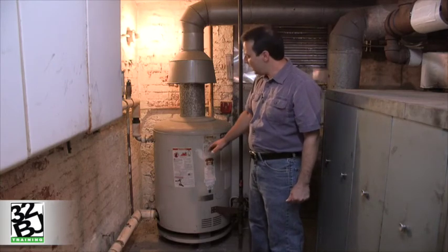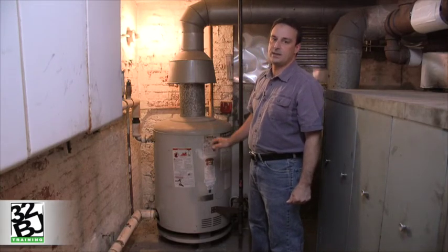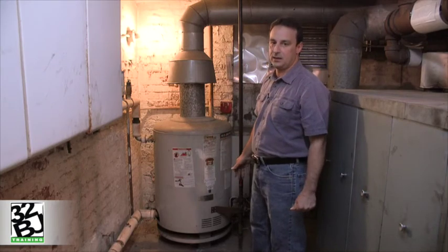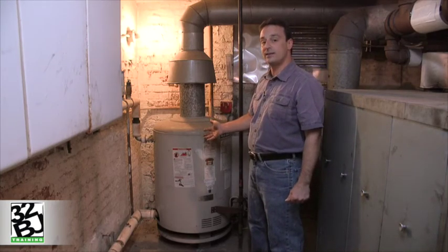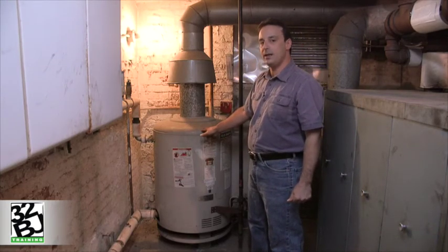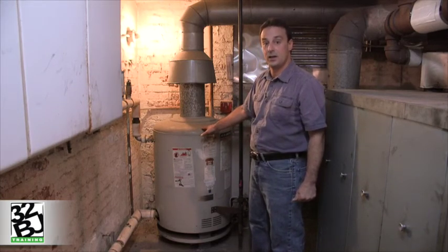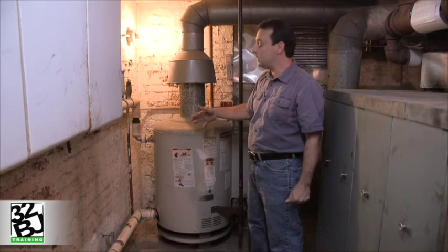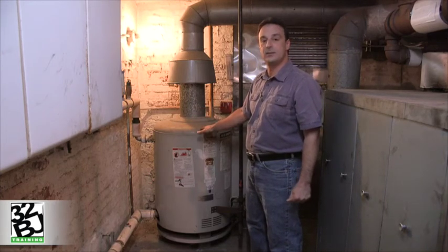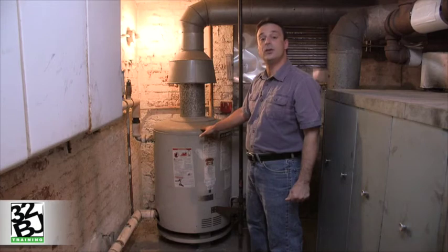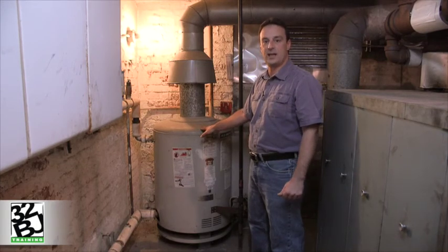Another inefficiency is the volume of water that this domestic hot water heater actually contains. For this 6-story residential building, this hot water heater volume is not enough to satisfy the hot water demand of the residents, so a large storage tank is also required for this system to function. This leads to even more inefficiencies that we'll take a look at.